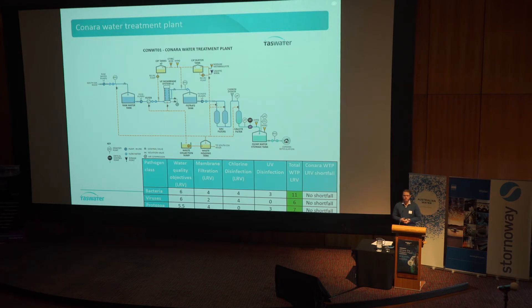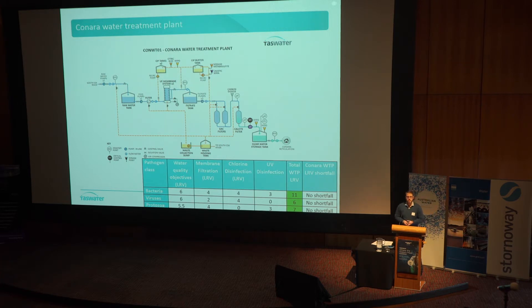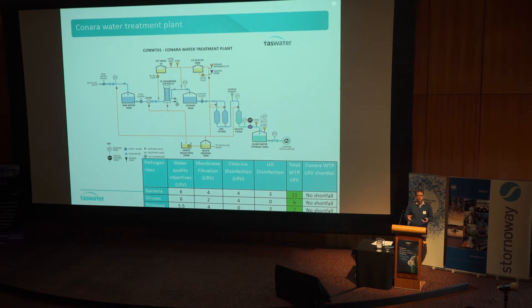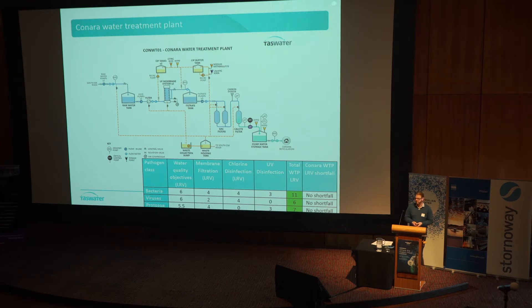So when we designed the treatment process, we took that catchment information into account. In terms of meeting our water quality objectives, we had three processes to remove pathogens: membranes, UV disinfection, and chlorine. You can see we're meeting our water quality objectives, and in some situations looking at a table like this you might think you've over-engineered it — you're getting 11-log bacteria removal. But the reality is treatment processes do what they do — you don't buy a UV system that does one log; they usually do three or four.